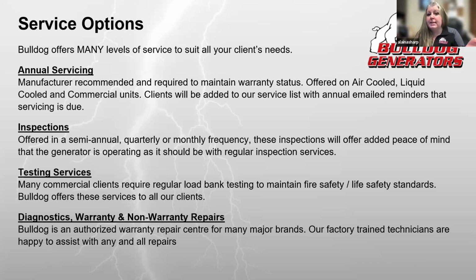They'll sometimes just do a semi-annual check, so we can go in, check on it, make sure everything's good, working as designed. And then we do the testing, like I mentioned before, with the load banking. This is for fire safety, just to make sure, because with a life safety unit for commercial buildings, that generator is supposed to be the last man standing in that building.